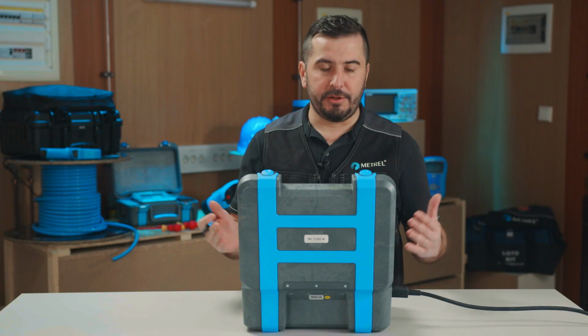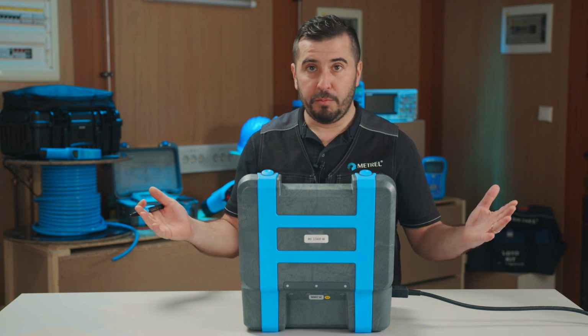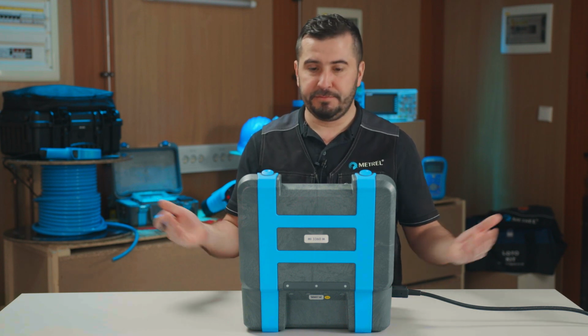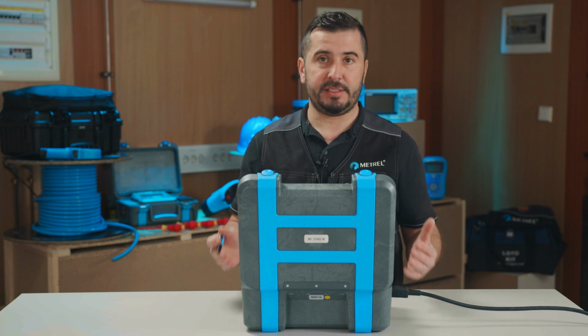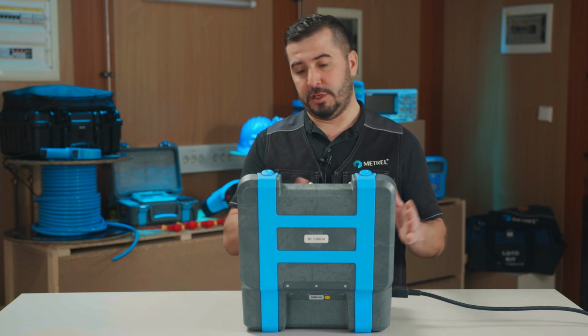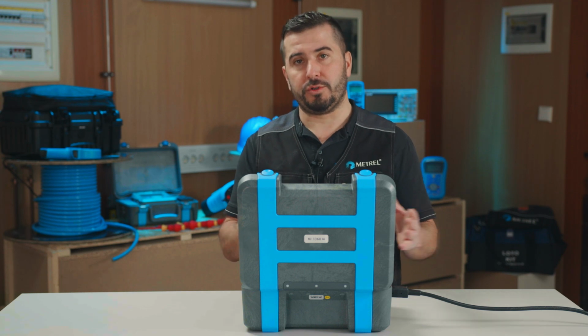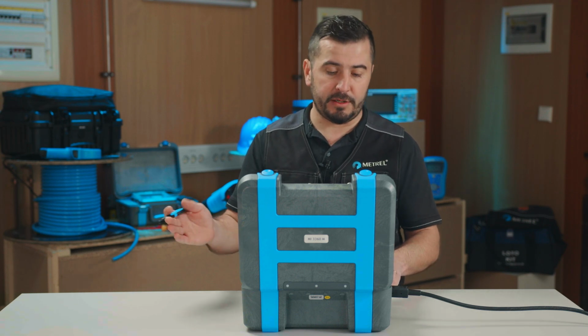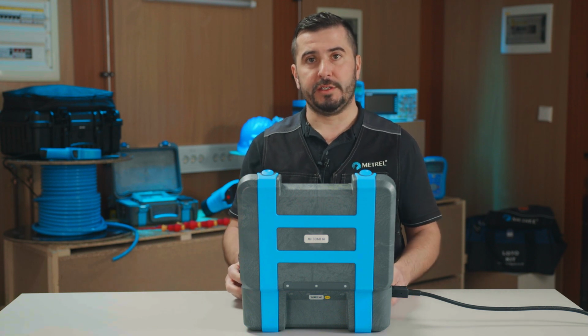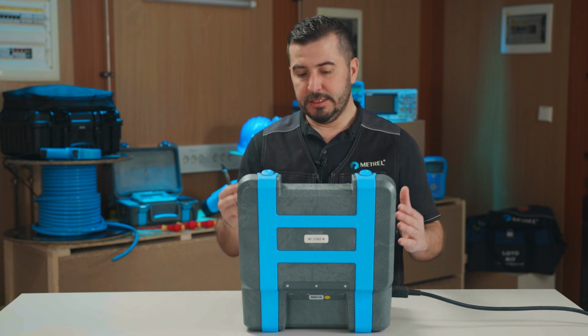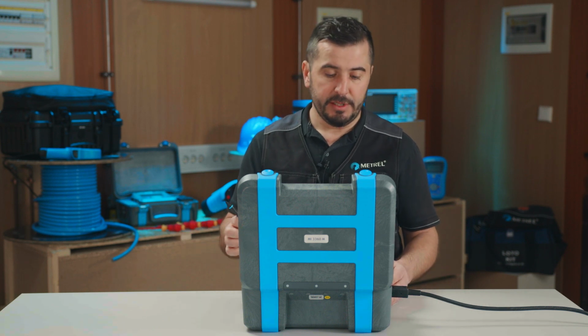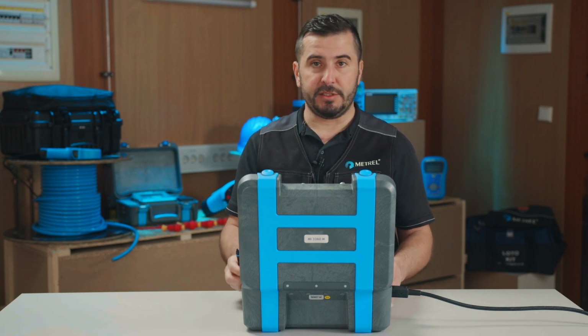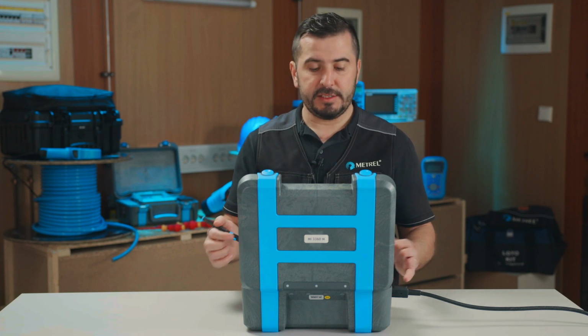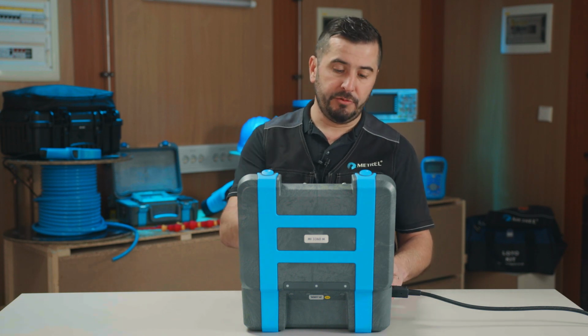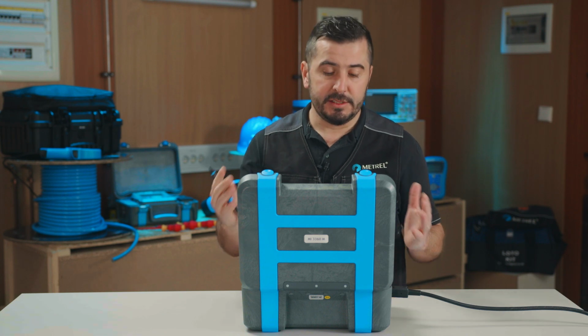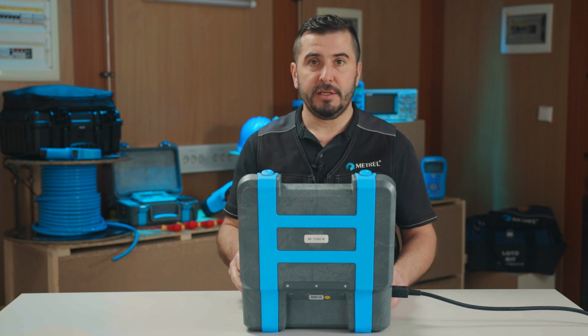Single test menu is probably not so interesting for portable appliance testing due to the fact that each single appliance has to be evaluated through the whole procedure, so meaning through the whole auto sequence. A bunch of tests have to follow one another to be sure that the appliance is checked accordingly and it's in good shape. But the instrument itself, so our appliance tester, has the ability to select each individual single test separately. This is inside here, let's say, mainly for troubleshooting.